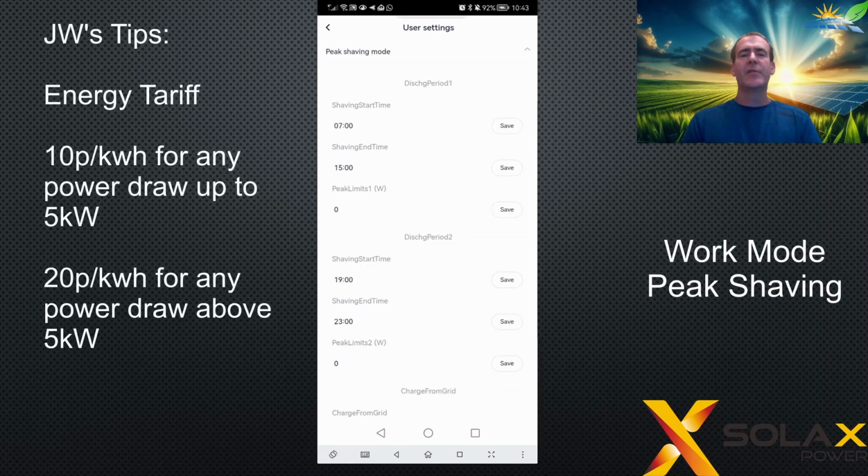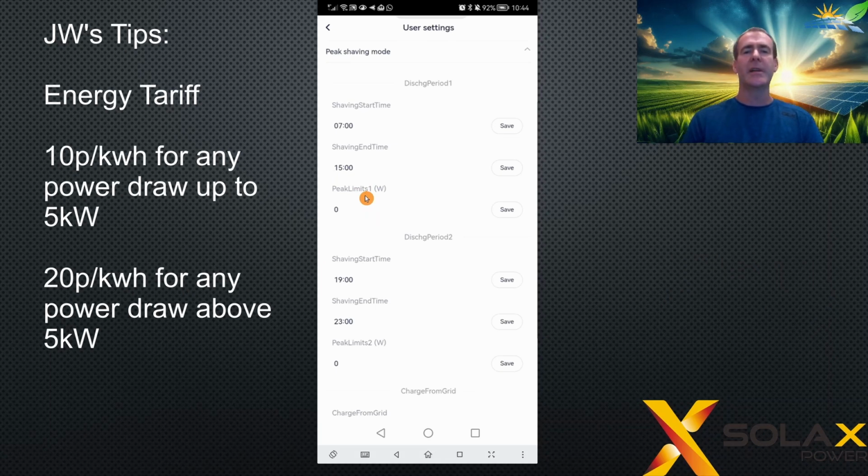So a use case scenario for peak shaving. For example, if your energy supplier was to charge you a certain amount for up to a certain power draw. So for example, up to 5 kilowatts, they charged a certain amount. Then anything that you used above 5 kilowatts, they would charge a higher amount. So you can set the peak limits wattage here to 5 kilowatts, and anything below 5 kilowatts will come from the grid, and anything above 5 kilowatts will come from the PV or the battery.